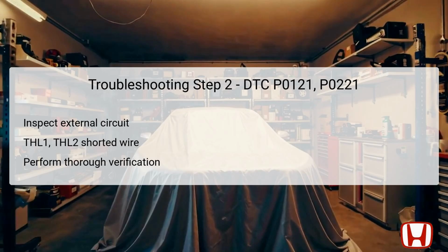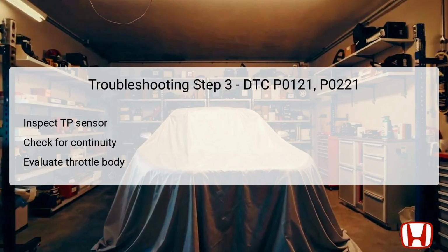With the connectors removed, the next step is to measure the resistance of the THL1 and THL2 wires to ensure they are not shorted. A normal resistance reading should exceed 1 megaohm. If readings fall below this threshold, it indicates a short in the wiring, requiring repair or replacement. Comprehensive verification at this step is essential, as it can often reveal foundational wiring issues that lead to problematic sensor outputs.